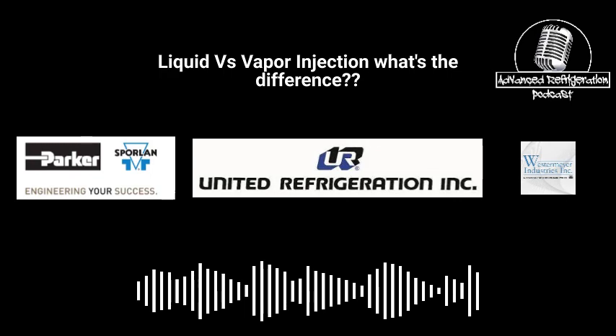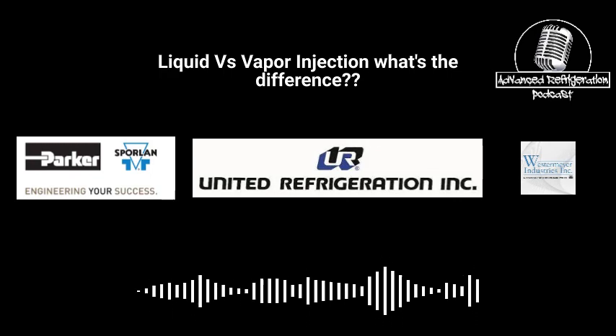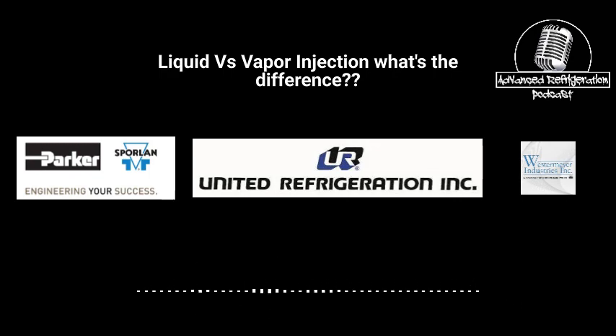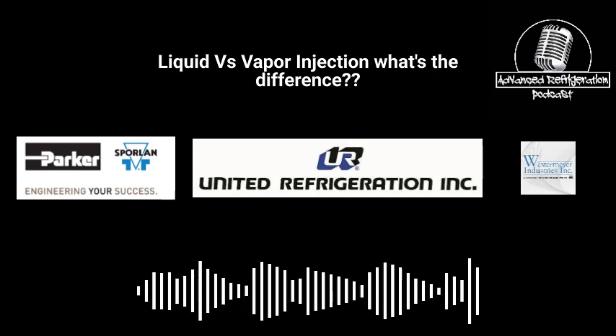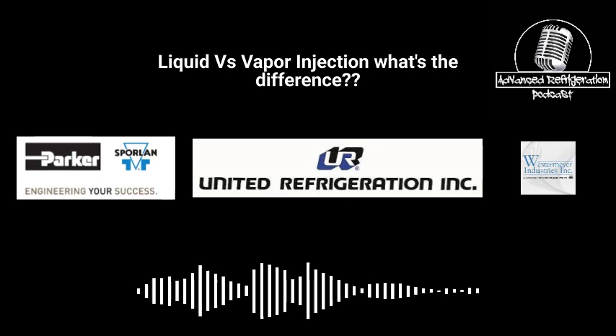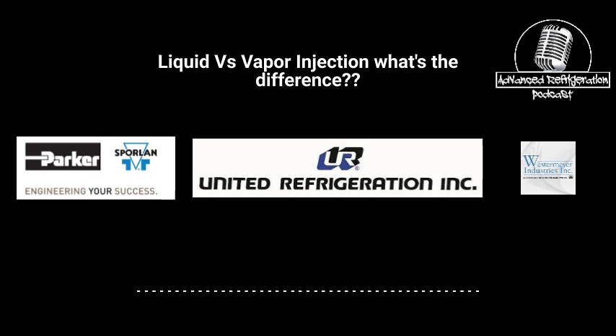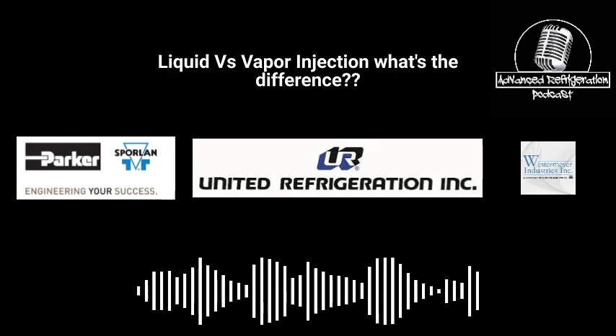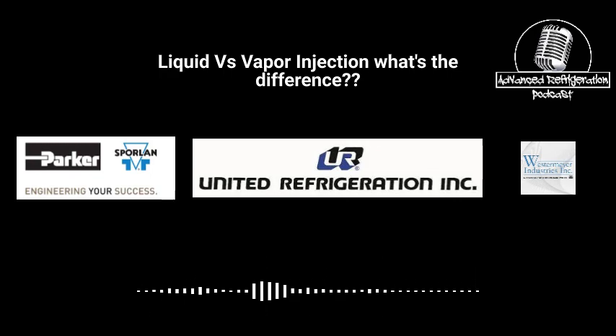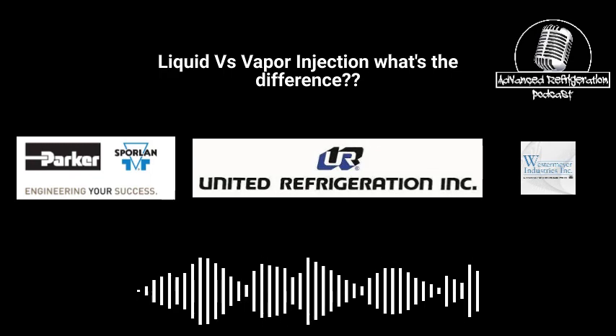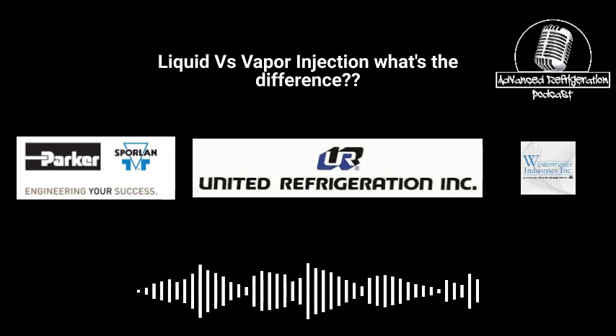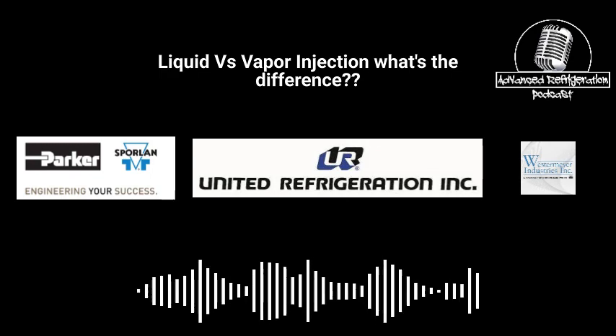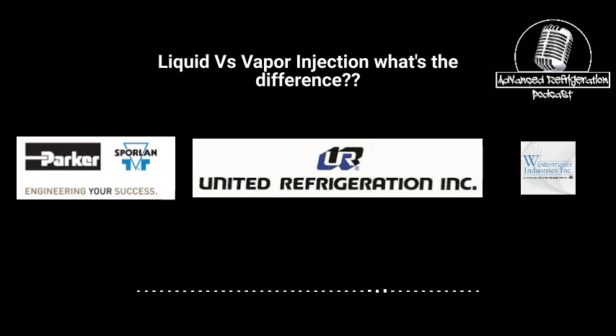Now, the nice thing about vapor injection is it cancels out. So say you have a subcooler and you want to run a subcooler on a rack. Now that subcooler is a load. I mean, nothing's free. You gain a little bit by subcooling the liquid down, but you still have to pay to refrigerate that liquid to cool it down. Now you bring in vapor injection. So we have to do two things. We have to cool the compressor. We were going to inject liquid before, but now we're going to use vapor injection. So that load you're going to use to cool the compressor is going to also subcool the liquid. So now you get this cancelization. You essentially subcooled for basically free for what you were going to use liquid injection for. So it cancels itself out.